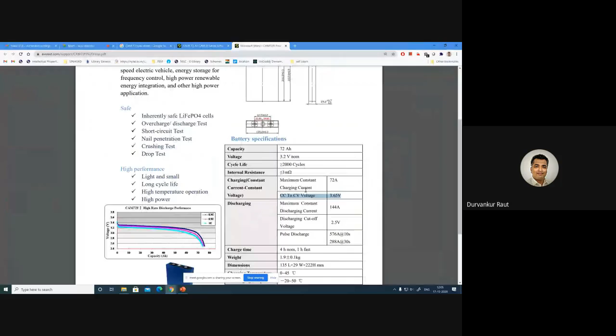Otherwise, they go into overcharge state, which is dangerous for us - dangerous from the point of view that batteries degrade faster, and it might lead to something called anode plating. Once the plating of the anode occurs, the capacity reduces first of all, and secondly, the internal resistance also increases, and that's what we call degradation of the battery.